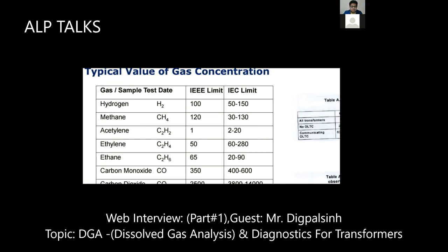Yeah, exactly. Some minor arcing, not visible by eye, but if there is some minor corona, that blue light, then only this value goes beyond 1 or 2. Okay. So you can say acetylene is a key gas for arcing, and it should always be noted. Yes. If you do DGA at the first 3 months and you find acetylene is 0.5 ppm, and after 6 months you find it is 1 ppm, that is fine. But again you do analysis at the next 6 months, at the half-yearly overhaul, and then it is 1.5. Then you have to note this graph, because it is increasing exponentially: 0.5, then 1, then 1.5. If some minor arcing or corona discharge is there, then only this value goes beyond 1.